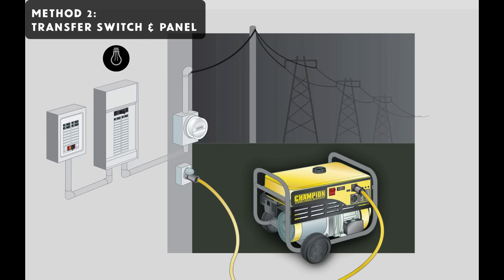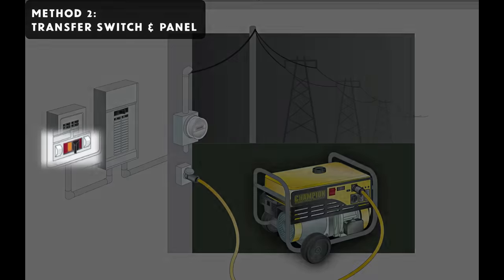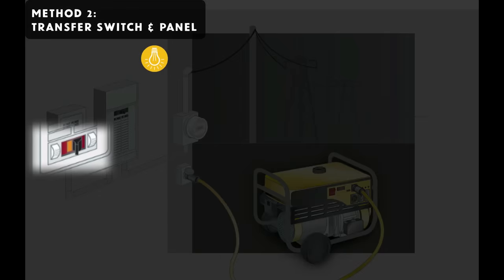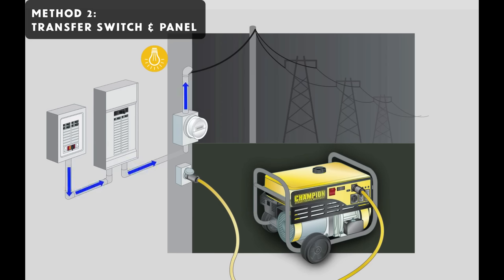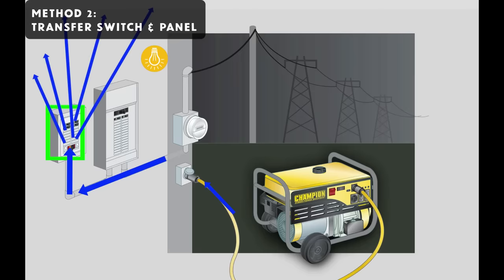At this stage, your generator's running, it's plugged in, but you still don't have any power to your home. For that, you need to actually manually flip the switch over. Like you see here, this switch is now in generator mode, which means that none of the power can backfeed through into the main panel and subsequently through your meter base into the lines. The only power involved is coming from the generator cable through the conductors in this conduit and then into the panel here where it is distributed to the circuits that have been identified ahead of time.